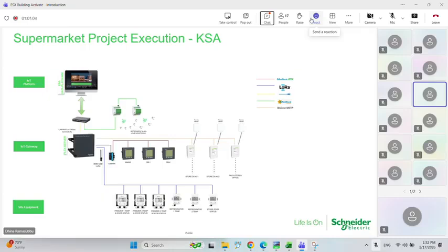And here as well, the customer's requirement was different. They wanted to digitalize their stores and make them smart stores. So what they had done is put Google Nest thermostats at the site, and they had a platform on which they were automating things. However, over a period of time, Google Nest started failing. The thermostats were not communicating properly with their dashboard, and the schedules were not working. So the whole intent of putting in Google Nest started failing, just because it's meant for homes, not for enterprise-grade customers.